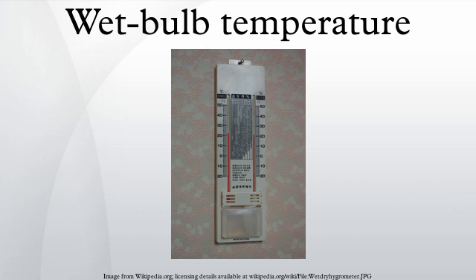Wet bulb temperature is measured using a thermometer that has its bulb wrapped in cloth — called a sock — that is kept wet with distilled water via wicking action. Such an instrument is called a wet bulb thermometer. A widely used device for measuring wet and dry bulb temperature is a sling psychrometer, which consists of a pair of mercury bulb thermometers — one with a wet sock to measure the wet bulb temperature and the other with the bulb exposed and dry for the dry bulb temperature. The thermometers are attached to a swiveling handle which allows them to be whirled around so that water evaporates from the sock and cools the wet bulb until it reaches thermal equilibrium.